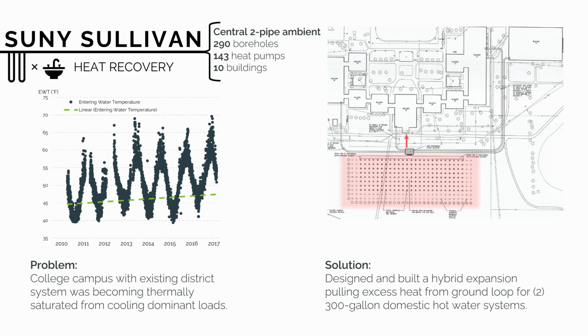This first one is SUNY Sullivan, a community college in the Catskills. I got to this job around 2017. There were 290 bores, 10 buildings, and 143 heat pumps. This system had been in service for about 10 years when I got there, and we got the BMS contractor to pull some entering water temperatures into the ground heat exchanger. It's not perfect and there's some data missing, but if you apply a linear trend line you can see it going up.